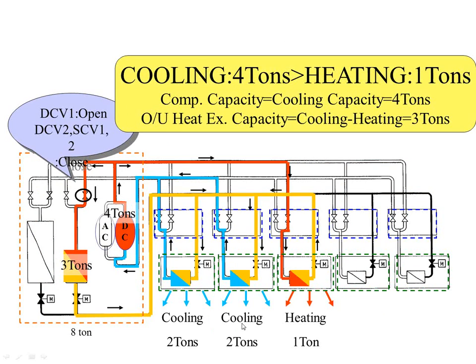When I switch this into a different mode, let's say everybody doesn't need heat. In this case, I have 2 zones that want cooling for a total of 4 tons, and 1 zone that wants heating for a total of 1 ton, right? So I need 5 tons of heating and cooling. But what I do is I close down my valves in the outdoor unit, so I only use 3 tons of the condenser coil surface area. And in this case I have 2 compressors. I'm only going to pump 1 compressor, at 4 tons. I need to move 4 tons of refrigerant for those 2 zones that want 2 tons of cooling each.